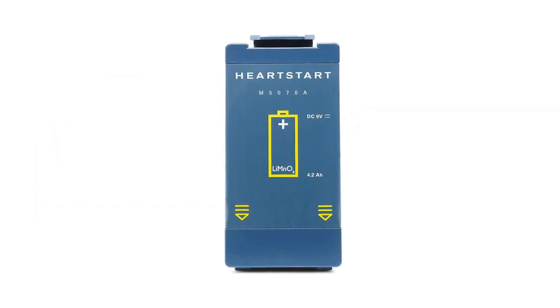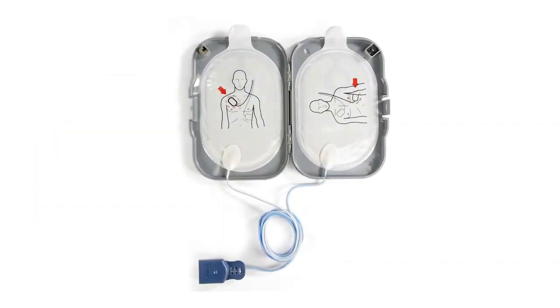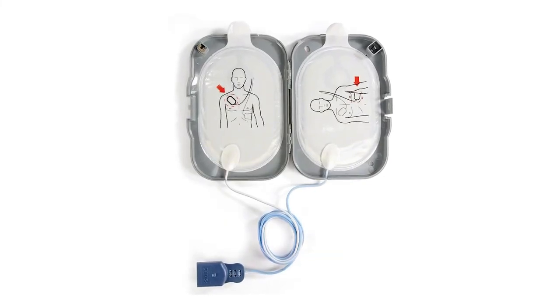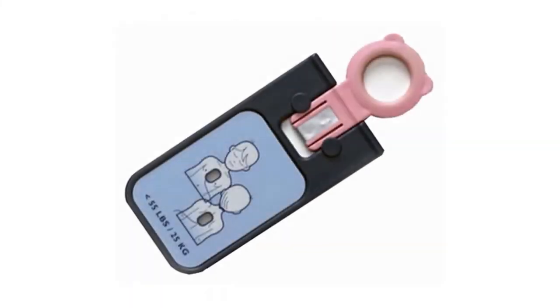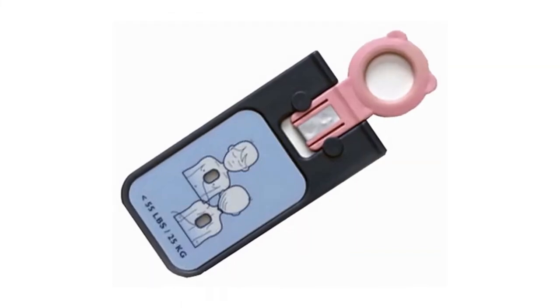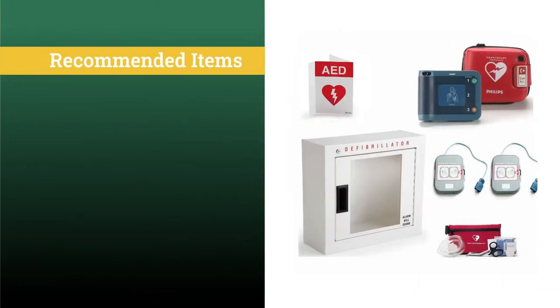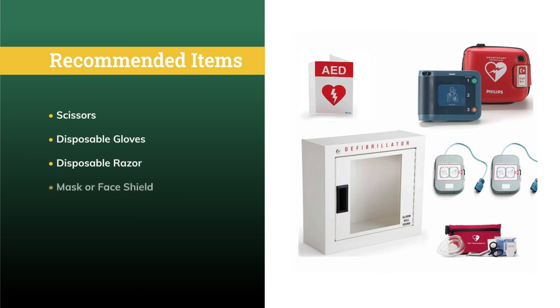It is recommended to have a spare battery and spare smart pads with the HeartStart FRx, and these can be purchased separately. It is strongly recommended to purchase the infant-child key, especially if the device will be in a setting where children are present. Other suggested accessories include scissors for cutting through clothing, disposable gloves to protect the user, a disposable razor for removing chest hair if the pads cannot make good contact, a mask or face shield to protect the user, and a towel or wipes to dry the skin for good pad contact. These items are available in a Philips Fast Response Kit.